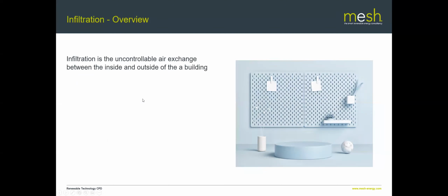So moving on to ventilation more generally, the first thing I'm going to do is define three things. The first of those three things is infiltration. Many of you will already be familiar with these three terms and will have a good understanding of them, but they are quite often used in the wrong ways, or used interchangeably where they're not actually interchangeable. So infiltration is all about the air that leaks into and out of a building in an uncontrolled manner. So it's not specifically designed to be there.